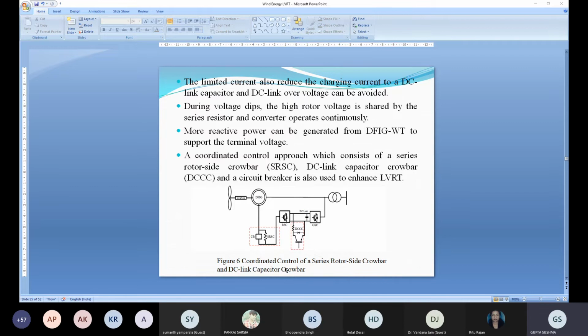capacitor, at that time we turn on this IGBT. So the extra energy stored in the DC link will be dissipated through this resistor. So the DC link voltage as well as the overcurrent are both taken care of with the help of this coordinated control type of converter. But we have to use two converters, at the rotor side as well as at the DC link side. So this is the advantage.